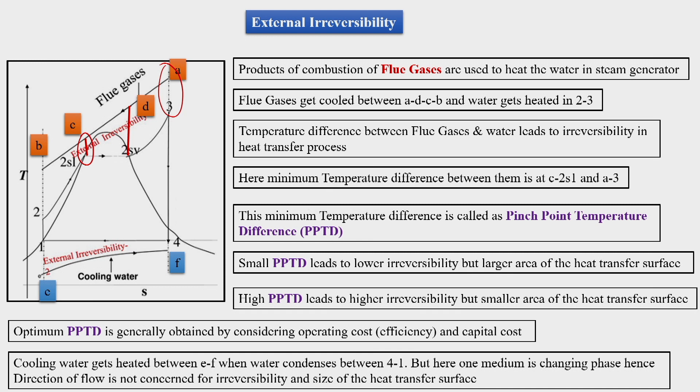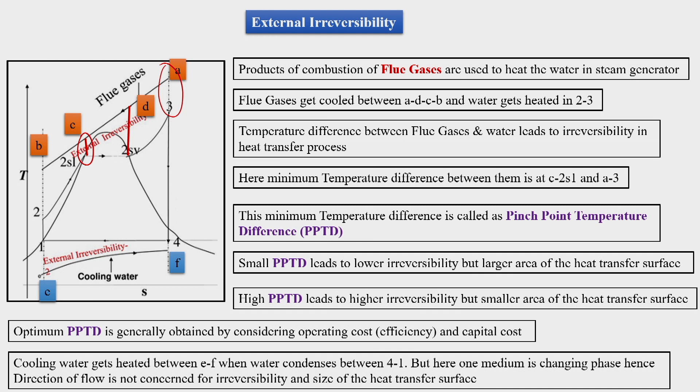Overall, there are external and internal irreversibilities to address. Internal irreversibilities are mainly due to friction and can be reduced by making passages smoother. External irreversibilities can be reduced by minimizing the temperature difference between flue gases and the steam passing through the steam generator.